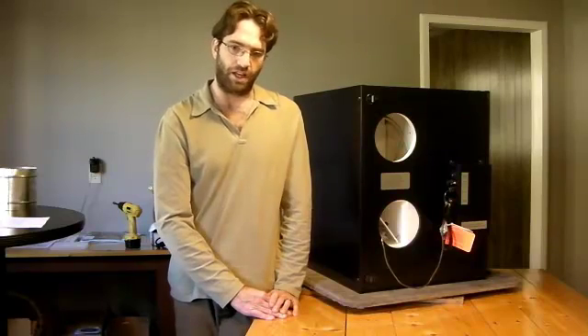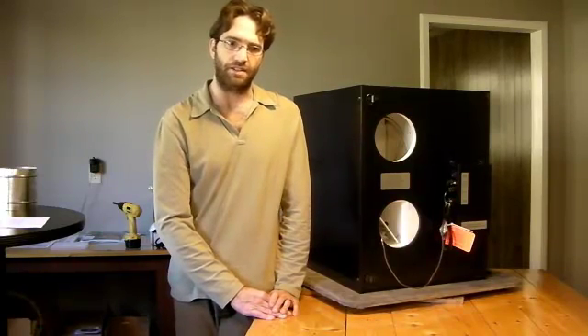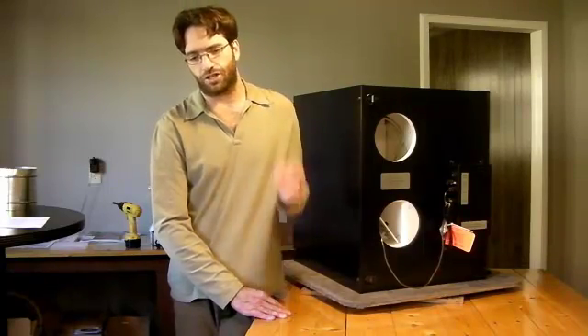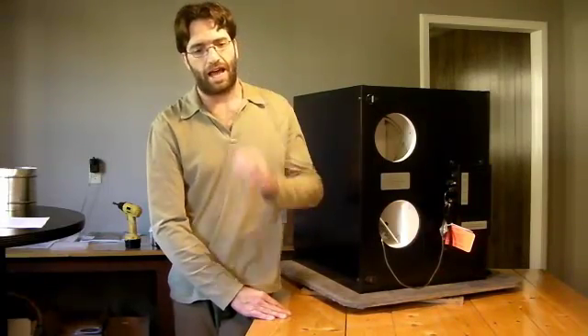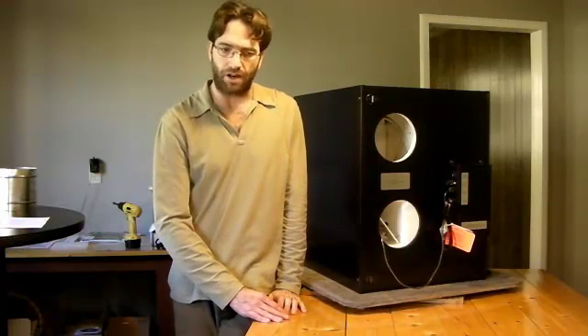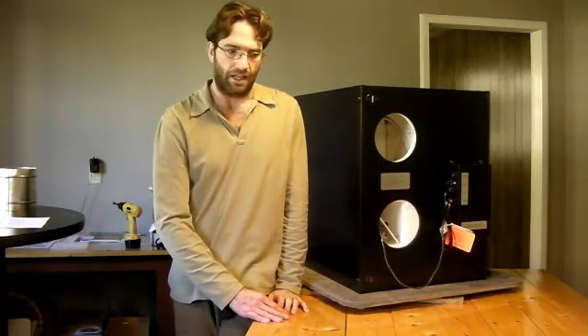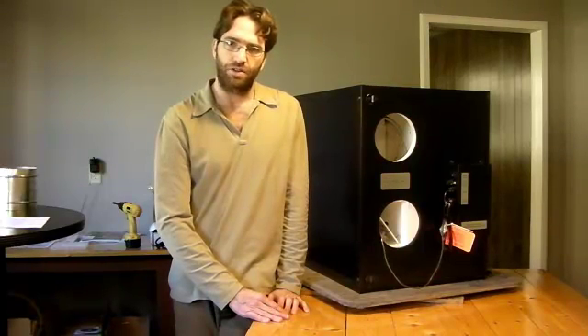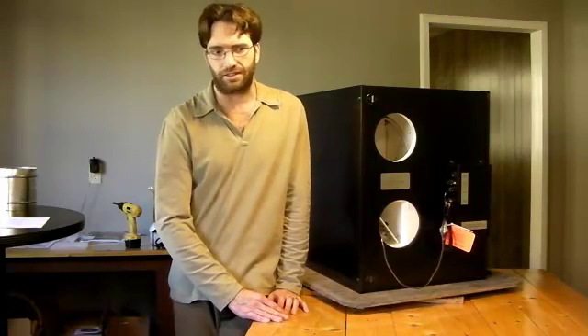Switching to if your house in the winter is too humid - like I said, both an ERV and an HRV are going to act as a dehumidifier. In that case, the HRV could be too fast. The ERV is going to retain some moisture in the house.